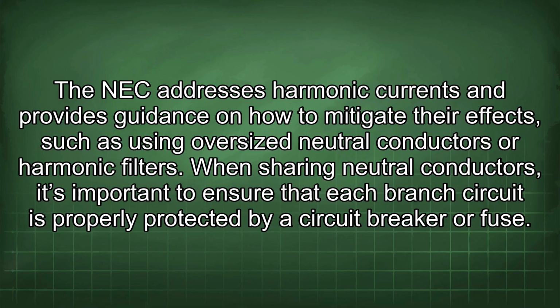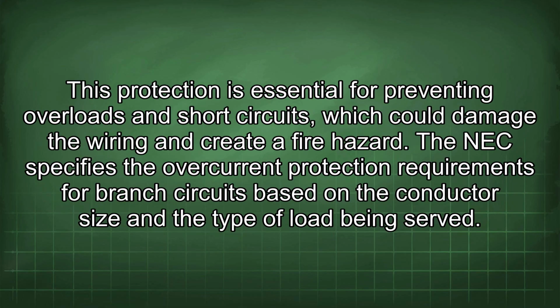When sharing neutral conductors, it's important to ensure that each branch circuit is properly protected by a circuit breaker or fuse. This protection is essential for preventing overloads and short circuits, which could damage the wiring and create a fire hazard. The NEC specifies the overcurrent protection requirements for branch circuits based on the conductor size and the type of load being served.